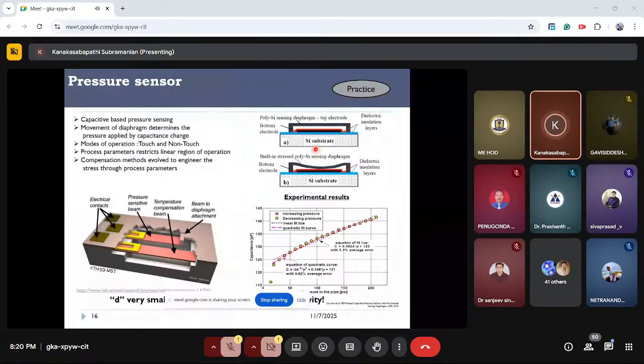The picture on the right is an illustration of a capacitive pressure sensor, with a diaphragm or membrane on top, shown in black, and a fixed electrode on the bottom. You measure the capacitance between these two, and in between them there is a gap that holds vacuum.